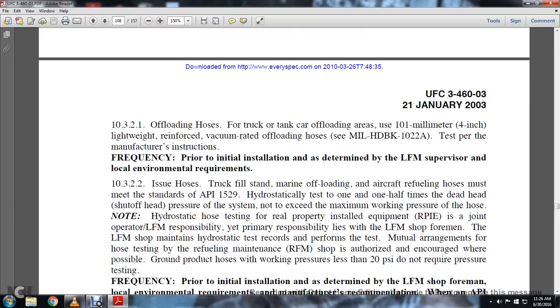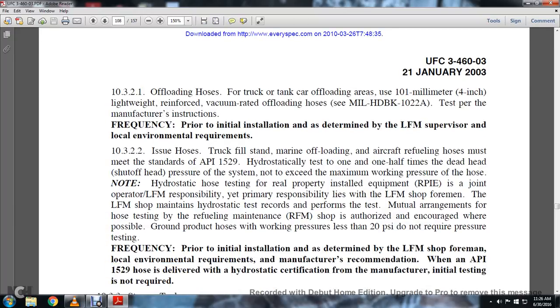Local environmental requirements. 10.3.2.2 Issue hoses. The truck fill stand, marine offloading and aircraft refueling hoses must meet the standards of API 1529. Hydrostatically test to one and one-half times the dead head shut-off pressure of the system, not to exceed the maximum working pressure of the hose. Note: the hydrostatic test of hoses on real property installed equipment, or RPIE, is a joint responsibility with the operator; the LFM shop foreman is primarily responsible. The LFM shop maintains hydrostatic test records and performs the test.